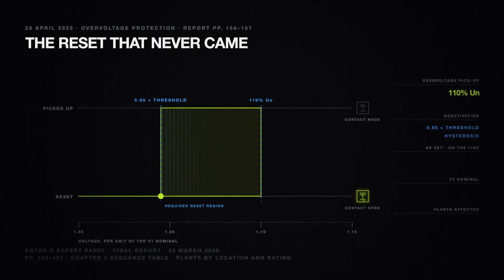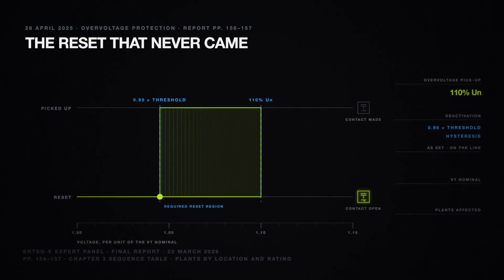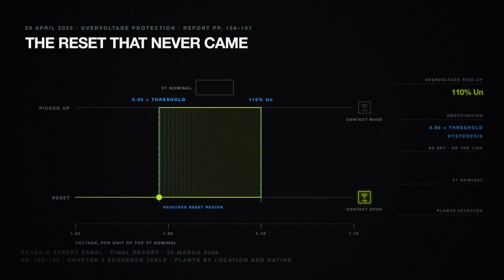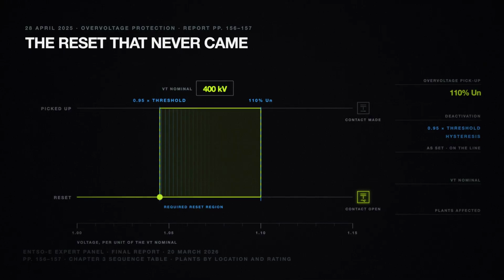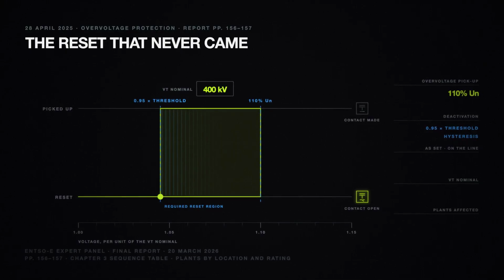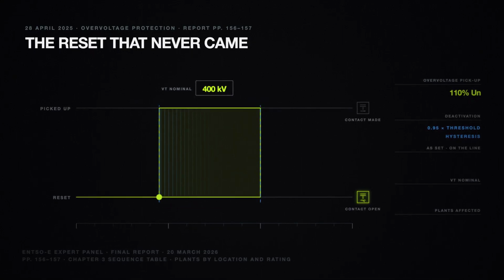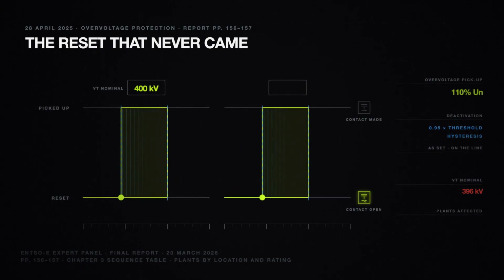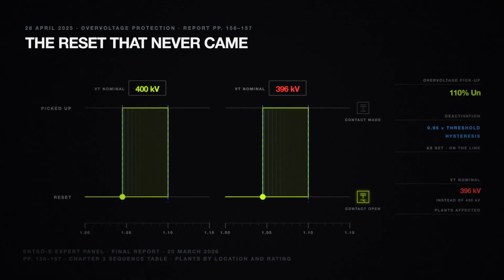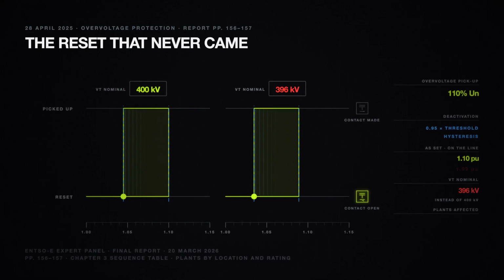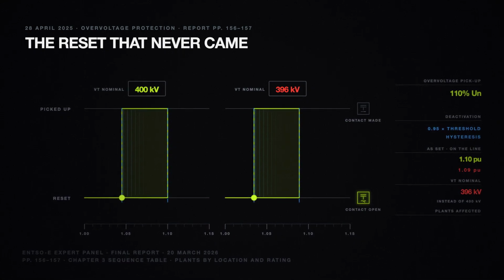The second cause is arithmetic, and it is smaller than that. A protection relay never sees the 400 kilovolt line directly. It sees a scaled-down copy of it through a voltage transformer, and somebody has to tell the relay what full scale is. At least 2 plants had been told 396 kilovolts instead of 400. 1%. The setting that looked like 1.10 per unit was, on the real line, 1.09.